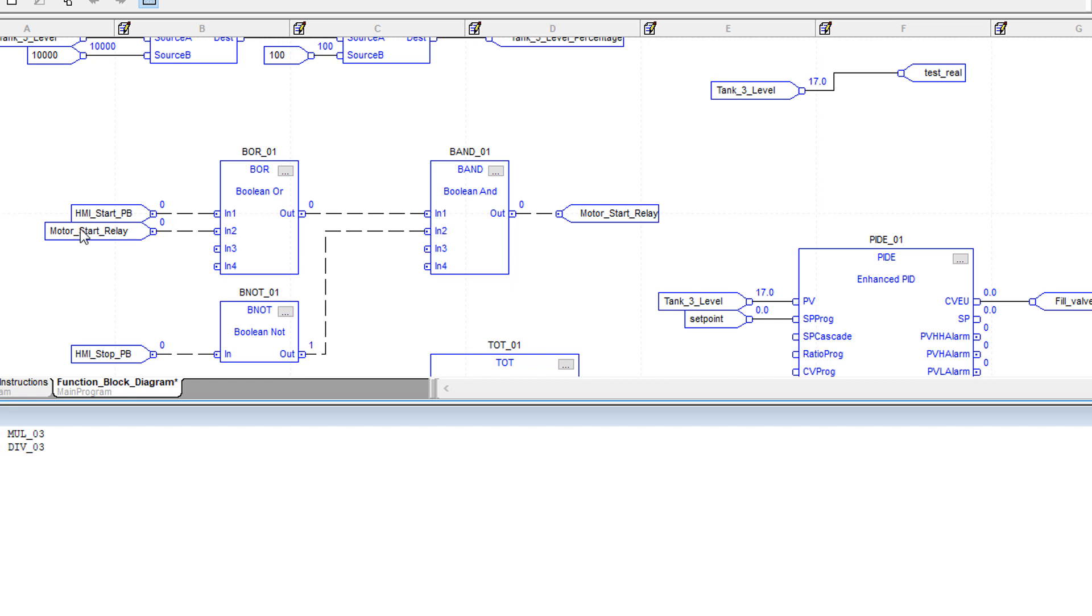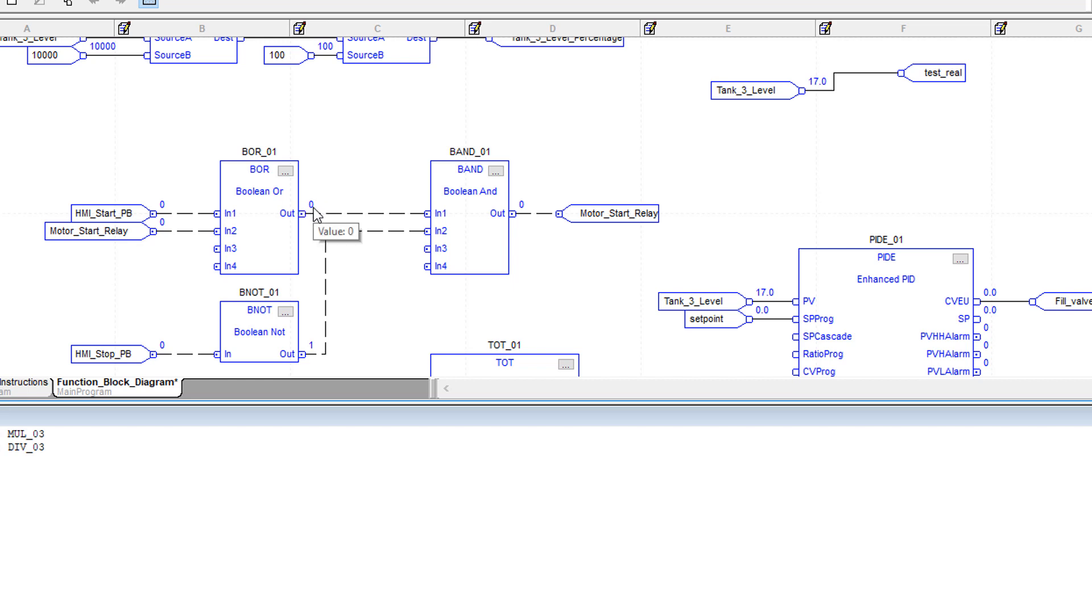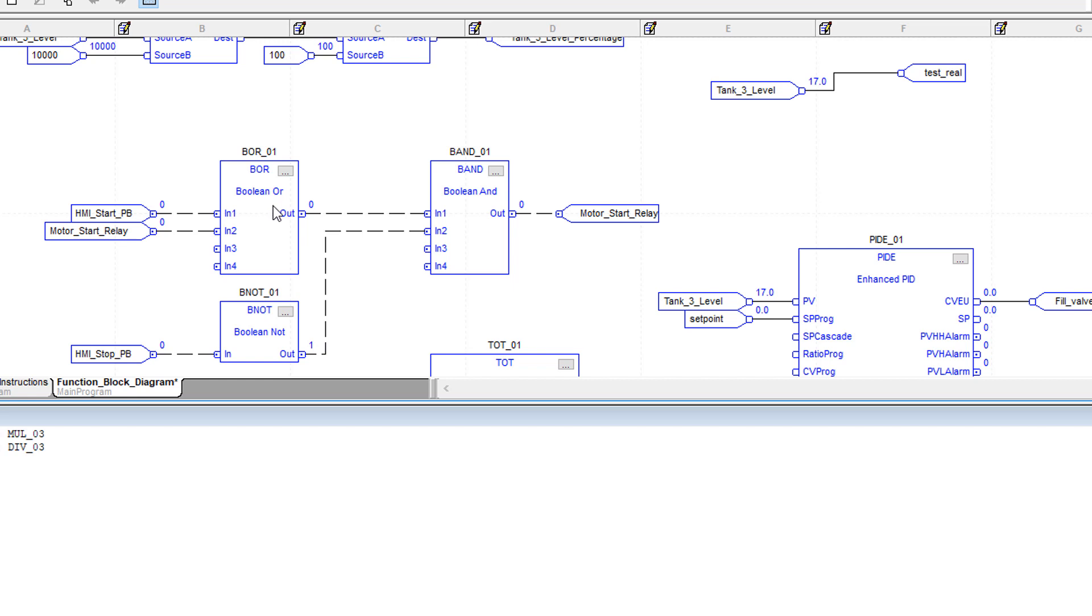If you're familiar with gate logic or using logic gates for Boolean logic, then it is actually pretty intuitive. But I think ladder logic is still more intuitive for simple Boolean logic personally. Let's just look at this example here. We've got a Boolean OR, a Boolean NOT, and a Boolean AND. The way this works is you've got four inputs for your OR. You can connect up to four inputs, and if any one of them is true, then the output is going to be true or one. If HMI start push button is true or if motor start relay is true, then it's going to output a one here.